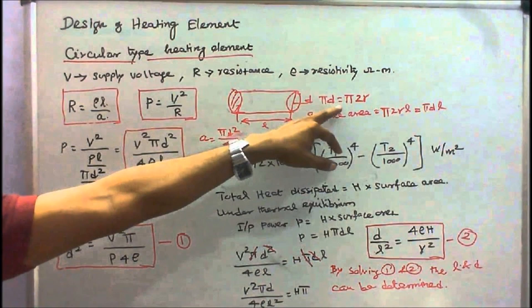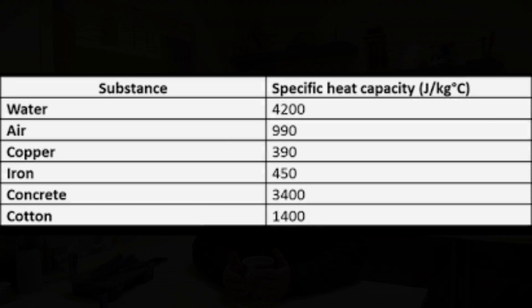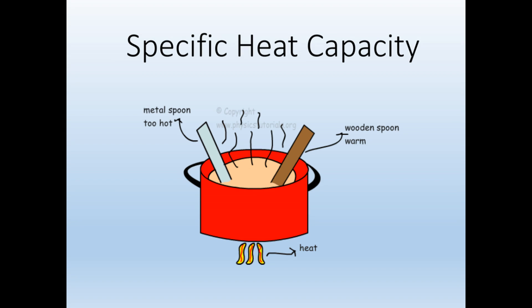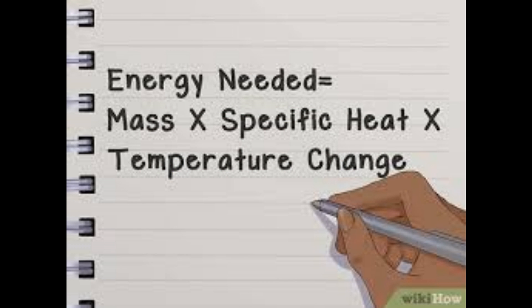The first place to start is: what is it that you want to heat? Luckily for us, there's only really two things we're interested in - that is the air for space heating and water for hot water. Materials have a property called the specific heat capacity. The specific heat capacity is the energy needed to raise the temperature of a material by one degree centigrade for a fixed mass. It's usually given in kilojoules per kilogram per degree centigrade. Water turns out to be 4.2 kilojoules per kilogram per degree, and air is 1.006 kilojoules per kilogram per degree.